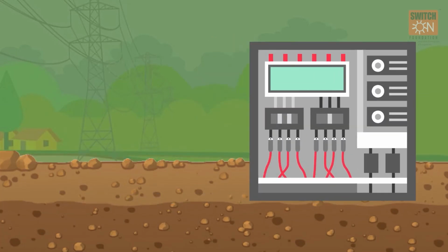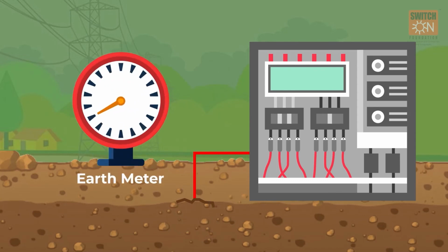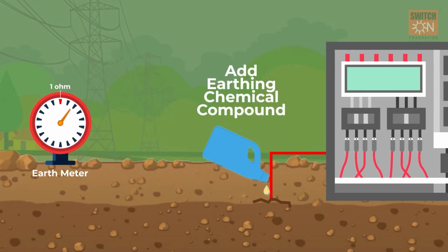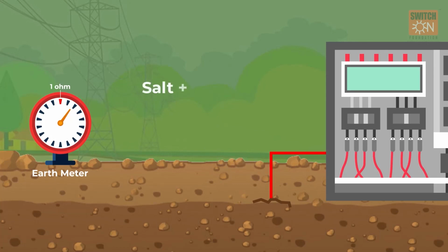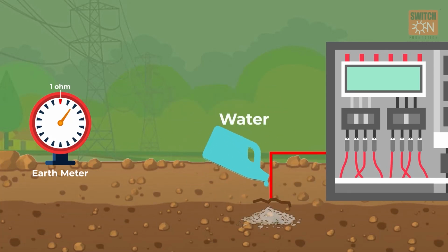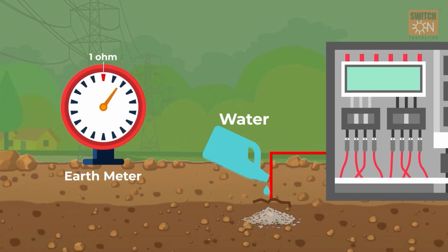Ensure that the controller is properly earthed and checked using an earth meter. The earth meter reading should be less than 1 OHM. If the earth meter reads more than 1 OHM, then earthing chemical compounds need to be added in the ground where the earth wire is inserted. Otherwise, a mixture of salt and charcoal can be used and water needs to be poured on it till a reading of less than 1 OHM is achieved.